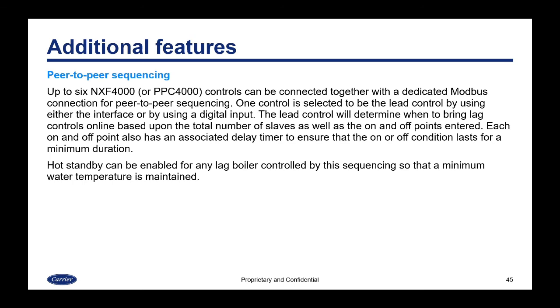Hot standby can also be enabled for any lag boiler connected by this sequencing so that a minimum water temperature is maintained. So with peer-to-peer sequencing, you have a lead boiler and it will determine if you need to bring on additional lag boilers to maintain the load.